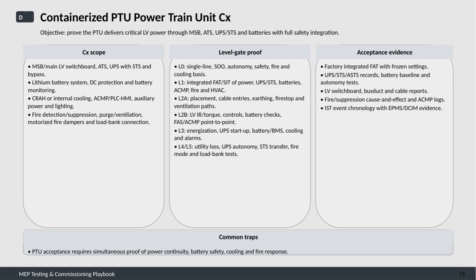The commissioning scope covers important components, such as the main LV switchboard, ATS, UPS with static transfer switches and bypass functionality, lithium battery systems complete with DC protection and monitoring, as well as cooling systems, auxiliary power, lighting, and fire detection and suppression equipment. We also look at ventilation systems, motorized fire dampers, and load bank connections to ensure comprehensive coverage.